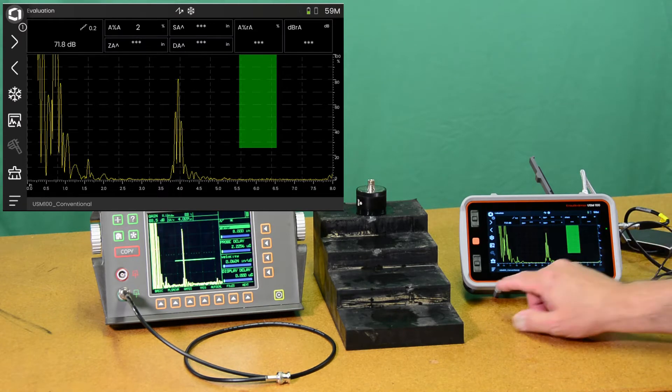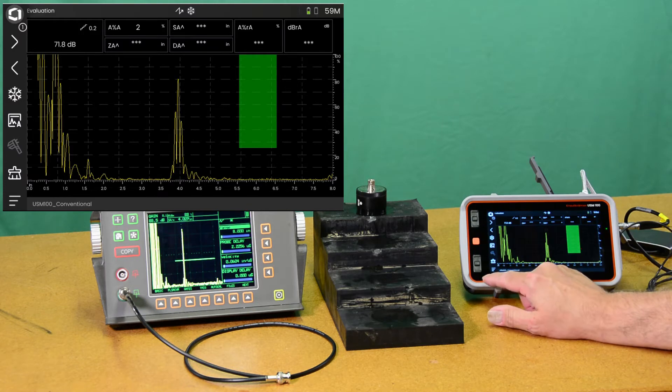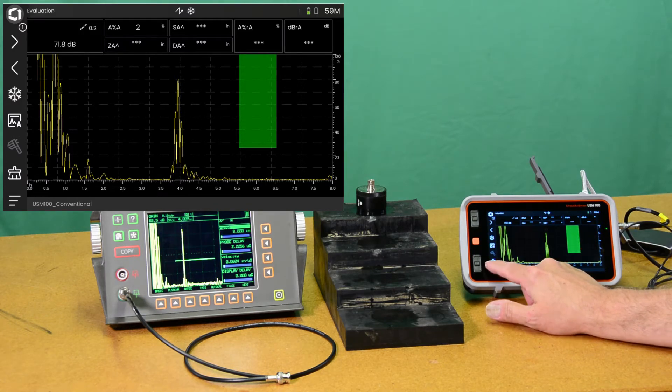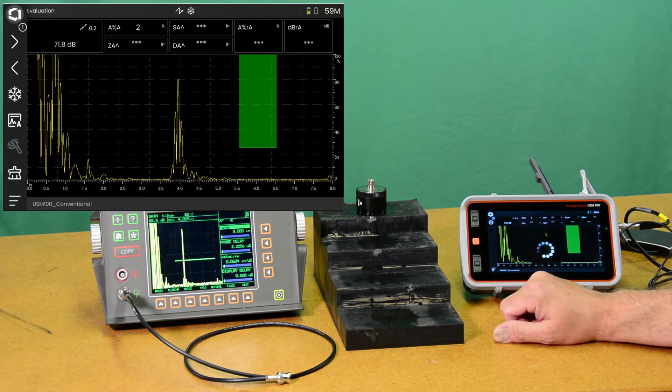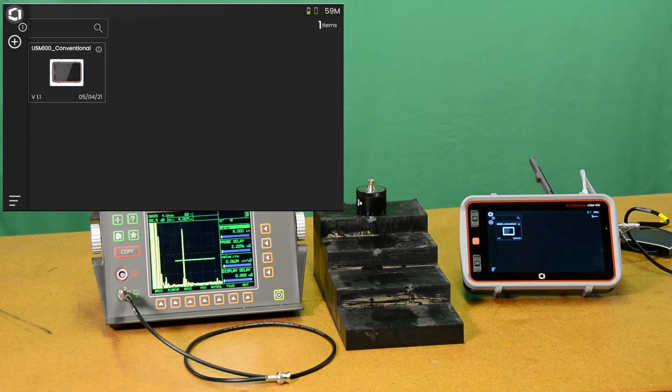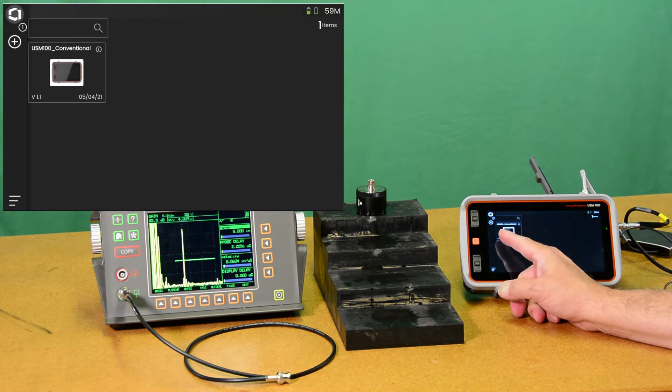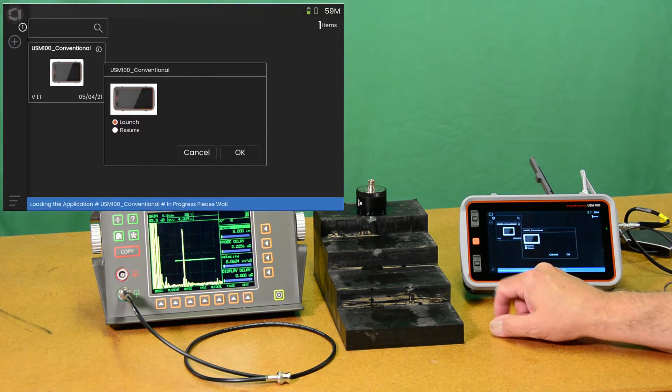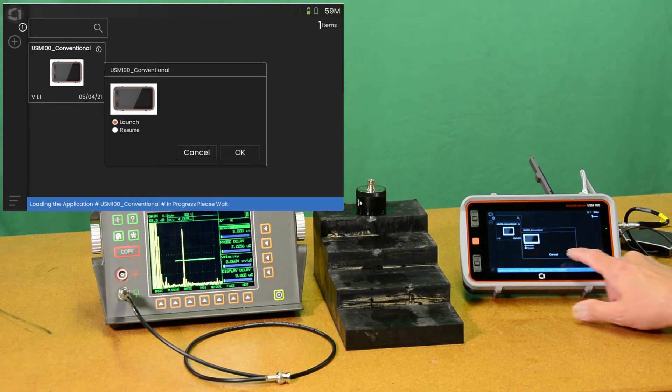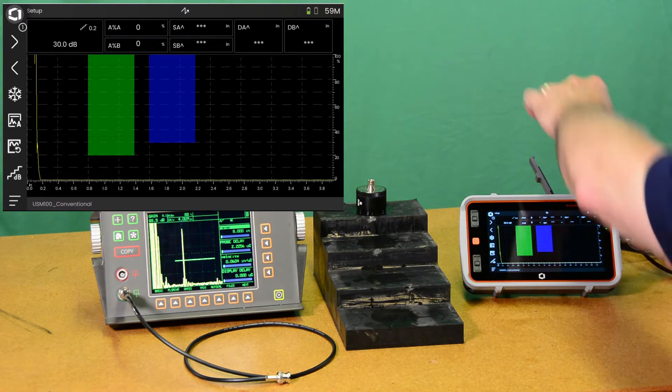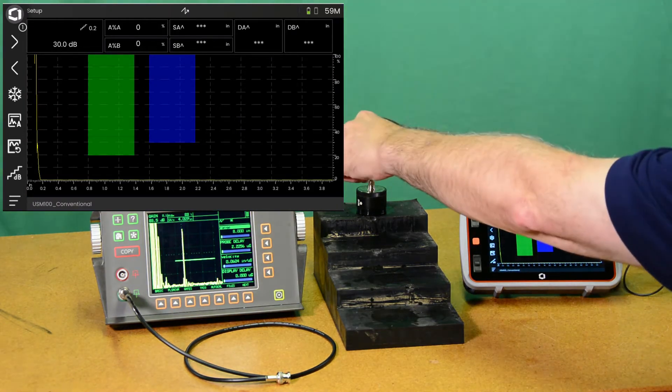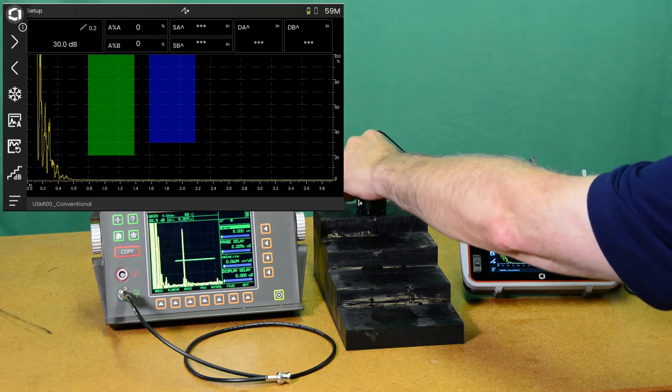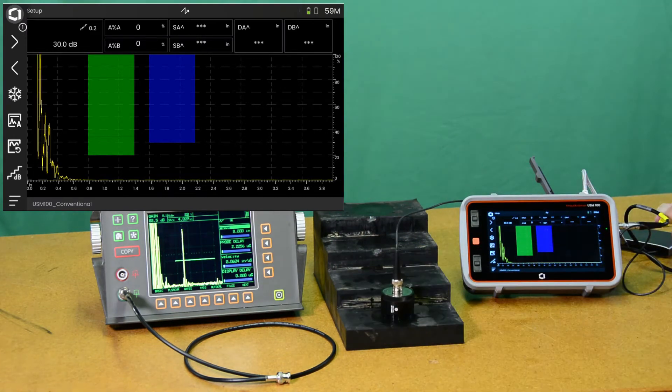So let's take this out of freeze mode and we'll start over from scratch and show you how we set the USM-100 up for this test. I'm just going to drop out of my app and we're going to be using the basic conventional app. I'm going to choose the launch option, which starts it from the beginning. I'm going to bring my probe back around here and connect. For now we're going to move down to the one inch step to aid our setup.